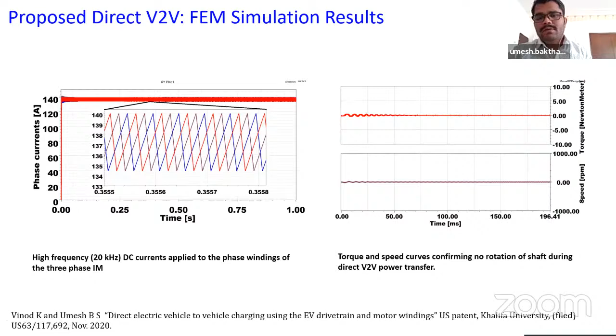The ripple is basically a convergence issue in the software, not due to the inertia of the motor — this ripple won't actually exist, as it will be damped by the inertia of the 150 kilowatt motor. So that's not a problem. Basically, the proof here is that the EV motor does not rotate due to the high frequency DC currents, which have a ripple percentage of 5% on a DC current average of 140 amps.